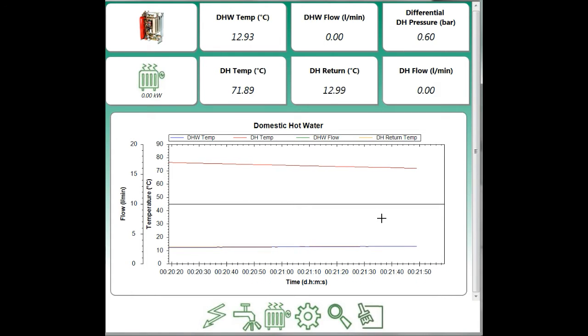The domestic hot water flow rate, green, is at the bottom at zero. We're not running taps at the moment. And the district heating return temperature in yellow, that's also at about 13 degrees C.